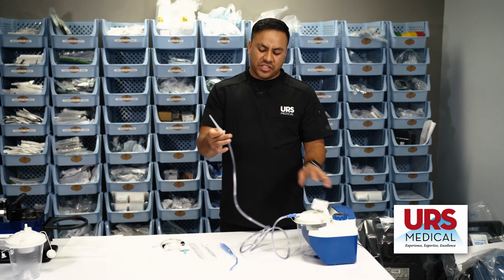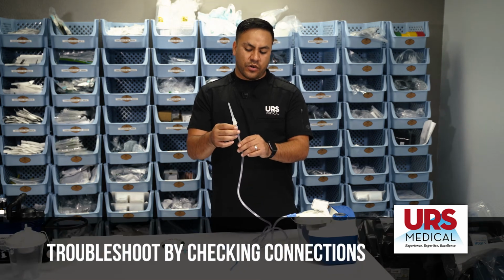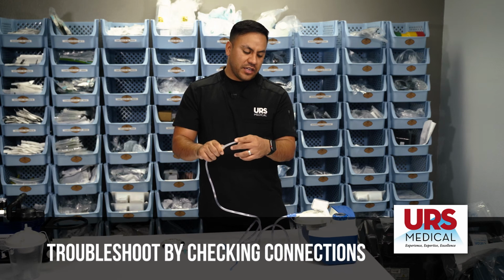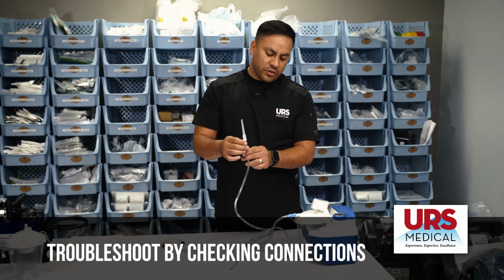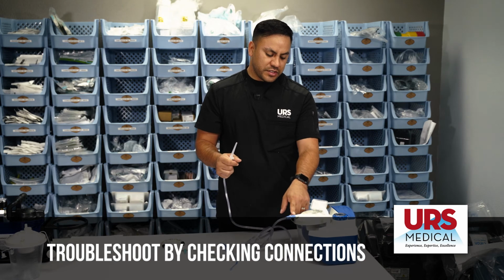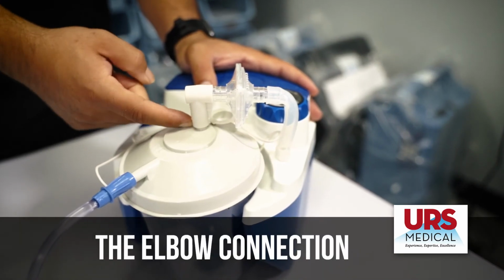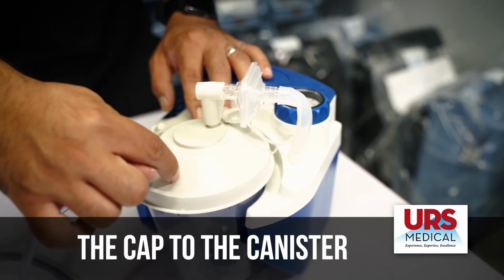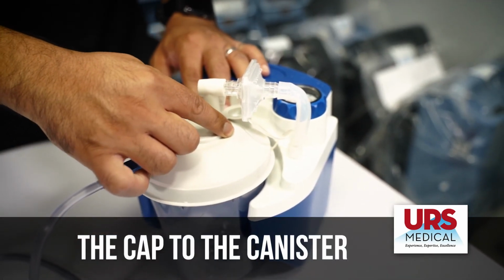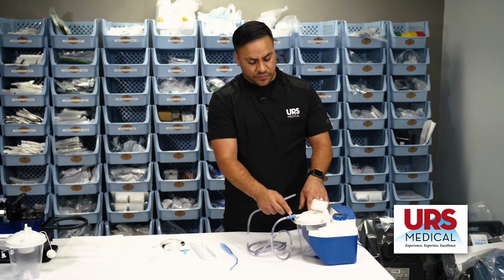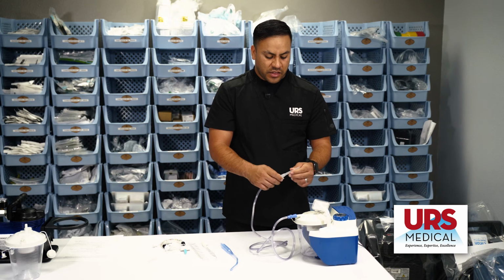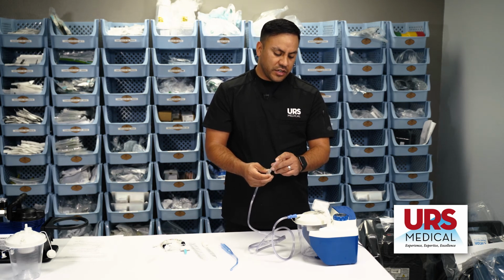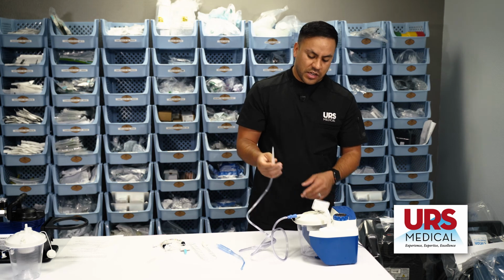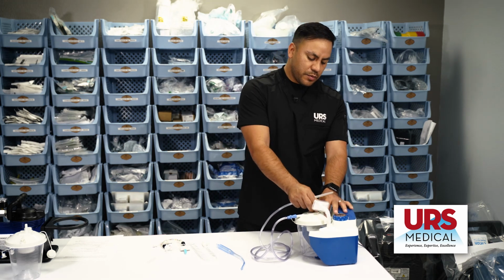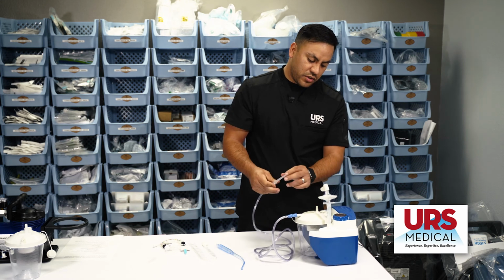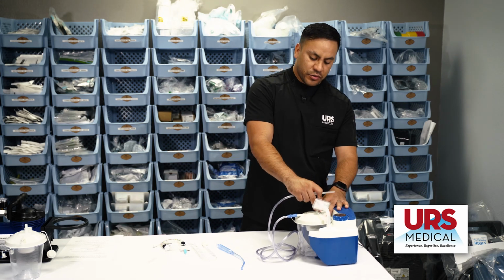For troubleshooting, you always want to check your connections, because if connections aren't right, you lose pressure and you're not going to generate that negative pressure. So the places you'll be able to lose pressure are at the connection points: the elbow where the connector connects to the filter, the cap to the canister, or where the tubing connects to the canister. Just make sure all those are connected and then you occlude the end, and if you're still getting a good reading, it means that the machine is working. If you do all that and there's not a good reading, say the elbow's off, and you do it, nothing moves, then you're losing pressure somewhere.